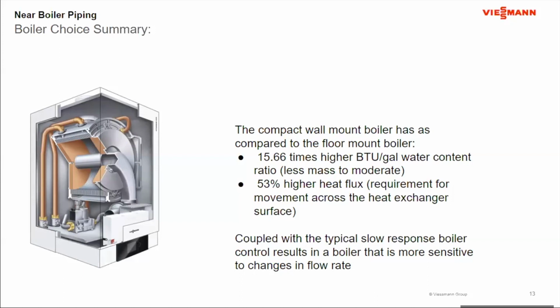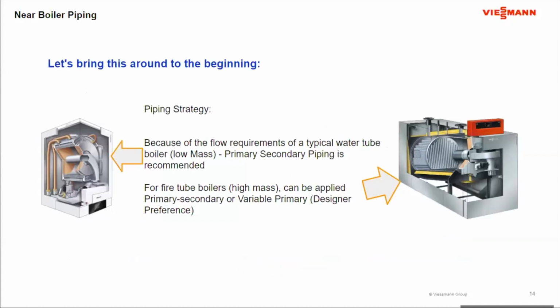You take this and you couple it with the typical slow response rate a boiler control has, you end up with a boiler that's more sensitive to changes in flow rates because of all of this. Okay, so what it really boils down to is when we start to look at making the decision between primary, secondary, or primary only, or variable primary, if you will. If I look at wall-hung boilers, because of the flow requirements of a typical wall-mounted, low-mass boiler, for all the reasons discussed, primary, secondary piping is recommended. So if I do a small-mass wall-hung boiler, it's going in primary, secondary.